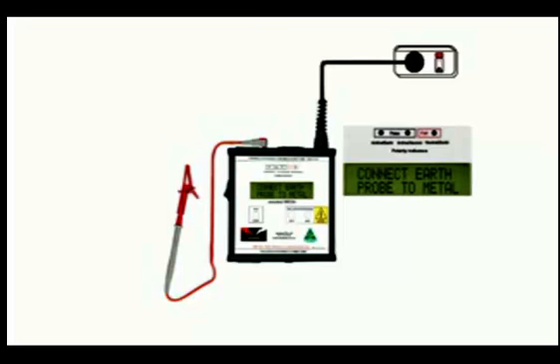Until we've tested an appliance, it's best to assume that it's got a fault until we've proved that it hasn't. So to be on the safe side, firmly clamp the test probe onto any exposed metal you can find on the appliance before you start the test. The bottom line is displaying the results of tests for leakage current, either for Class 1 or Class 2. Doesn't matter which one we have, it's testing for both anyway.